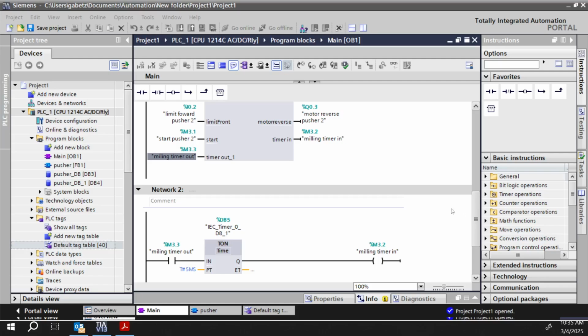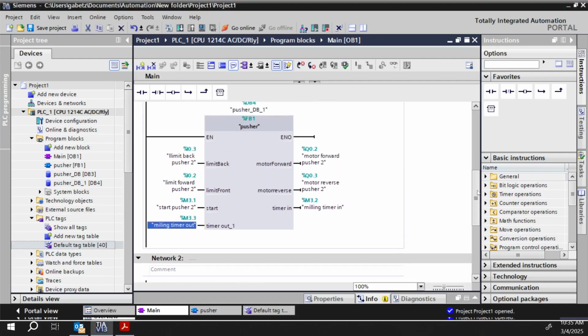So anyway, that is our function blocks in a nutshell. You can use them for organization: put all your stuff related to different sections inside the code, hard code all your input and output values, and that will be fine. Just make sure you call it from the main block. Or you can use them how they're supposed to be used and write code in there using variables that you then feed inputs and outputs to. That way you can make your decisions based on these things.